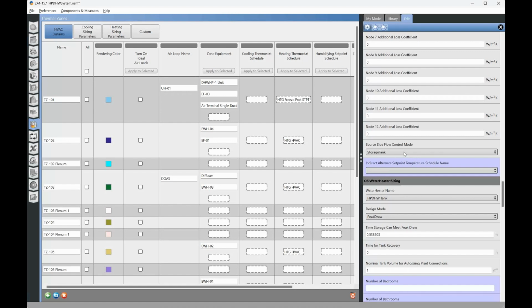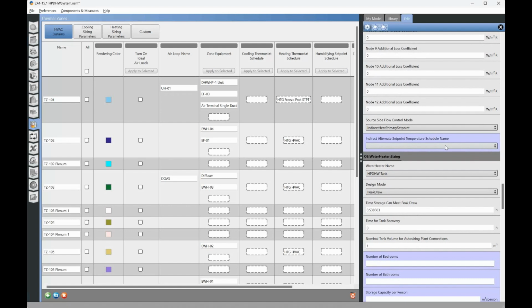Well, all of these have to do with requesting flow to the compressor, but we'll just keep the default set point, because right now we have the compressor supplying 140 degree water, and the heating elements will supply 120 degree tank temperature as a sort of backup, in case the compressor is not operating or it's unable to provide the heat input needed to satisfy the demand.